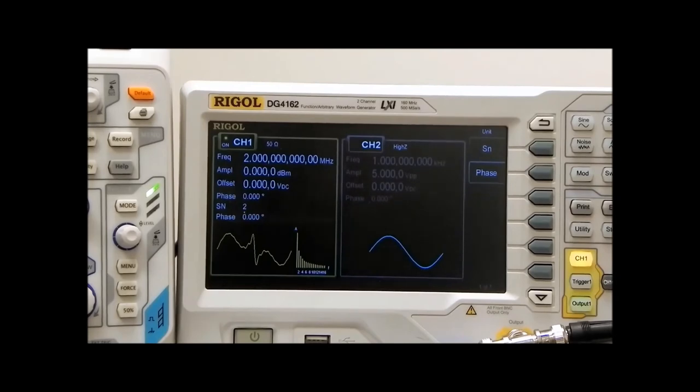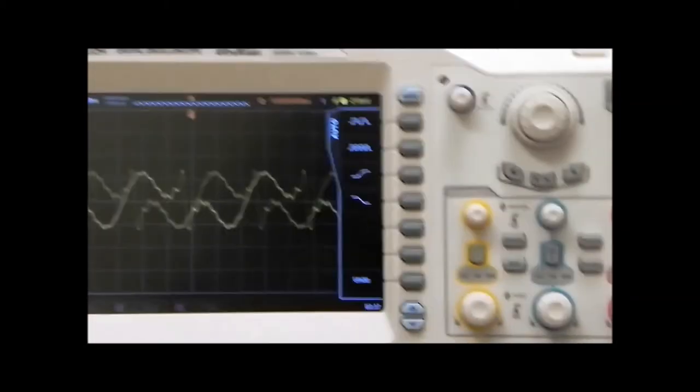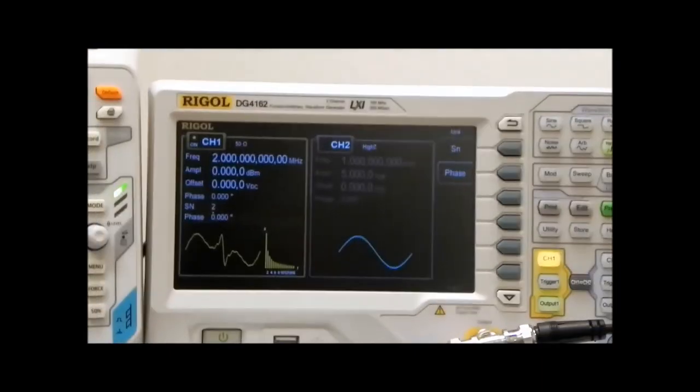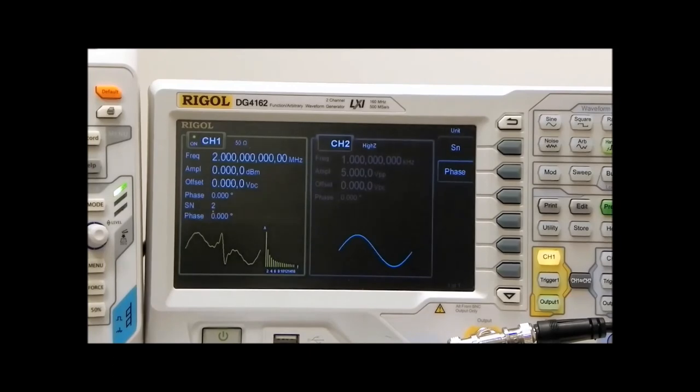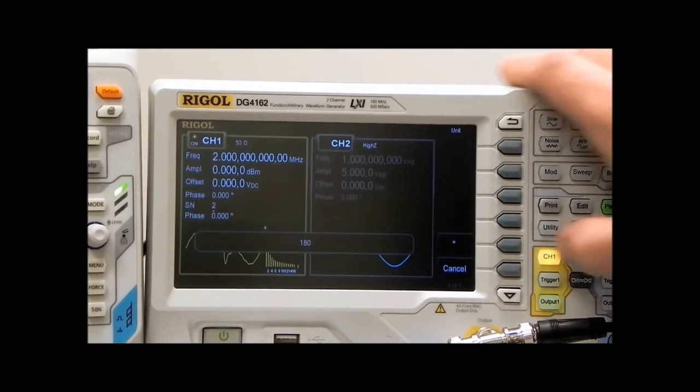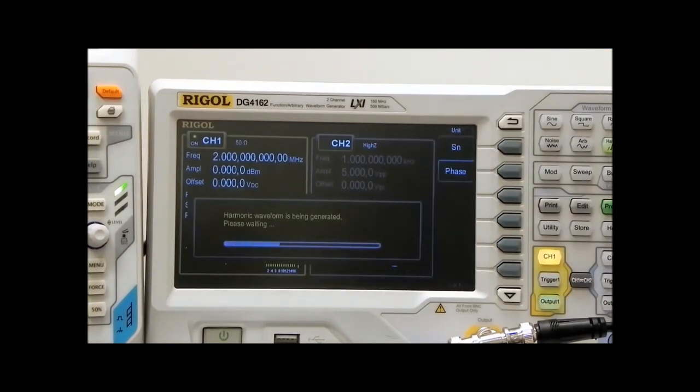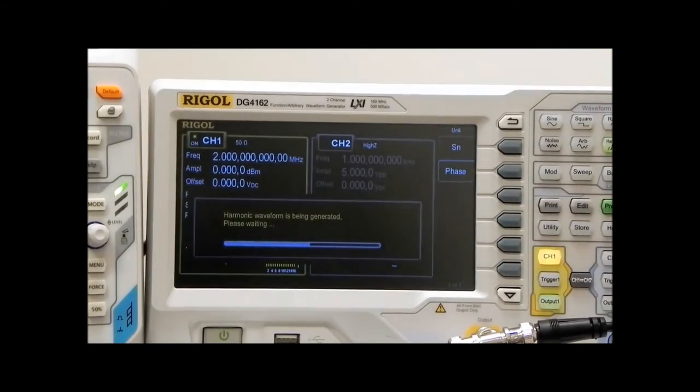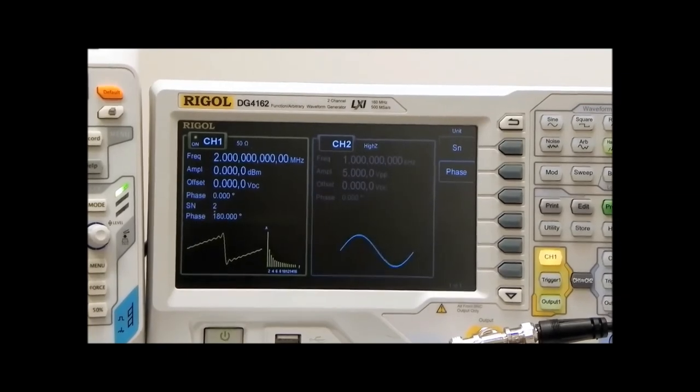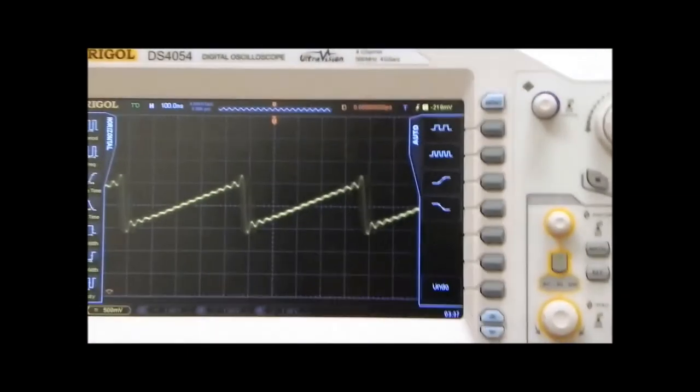shows that on the panel for the generator, and it shows up quite differently in time on the oscilloscope. And if I go back here, I can reset it back to 180 degrees and recover my signal. And pretty soon, you'll see that we are back right there.